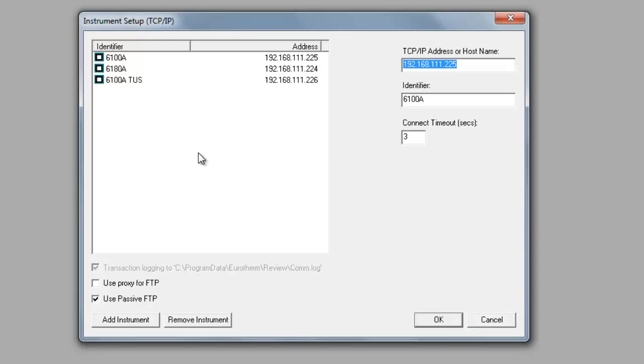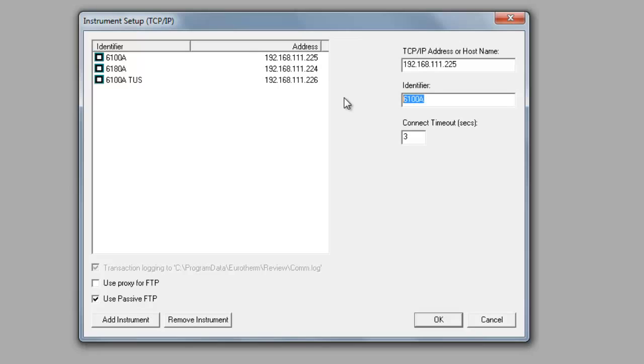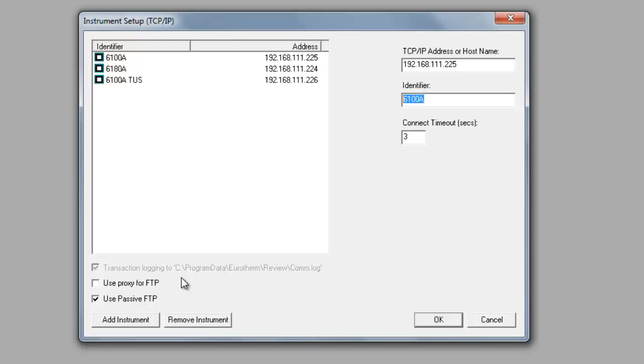The nice thing about this is you don't have to plug in a USB stick, walk over to your computer and dump the information. This is all done over Ethernet, it's very simple, literally a couple of clicks and you're done. Just talking about this screen, it's as simple as plugging in the IP address of the recorder. You give it a unique identifier, which I would recommend naming the exact same thing as your recorder. The connect timeout, meaning how long it takes before it can't connect to the recorder, I would leave that as three seconds, which is the default. And lastly, at the very bottom here, you've got use passive FTP, which essentially gives you the ability to bypass maybe third-party software like McAfee firewalls. It doesn't hurt to use it, so I'd recommend using it regardless. When you're done setting this up, you can simply click OK.